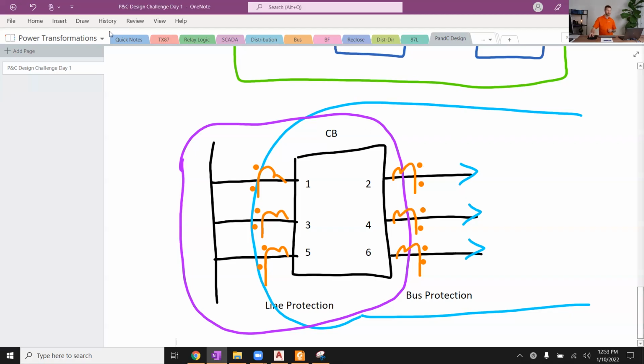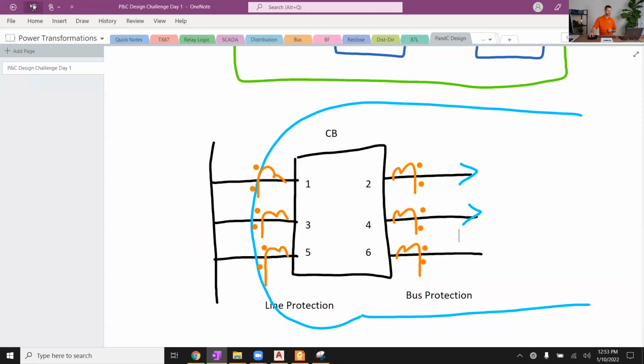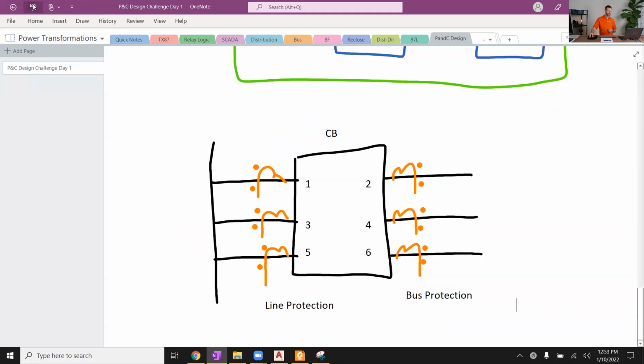I'm going to remove those zone of protection lines to not clutter it up too much as I add another thing to this drawing, but hopefully that gave you that concept there. So again, I would call this the bus side CTs. This is the line side CTs. And we're using bus side CTs to protect the line, and we're using line side CTs to protect the bus. Keep that flip terminology in mind.